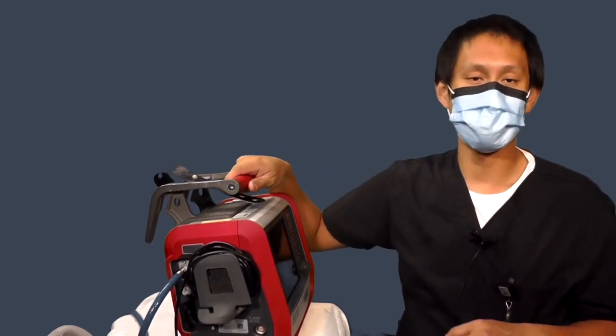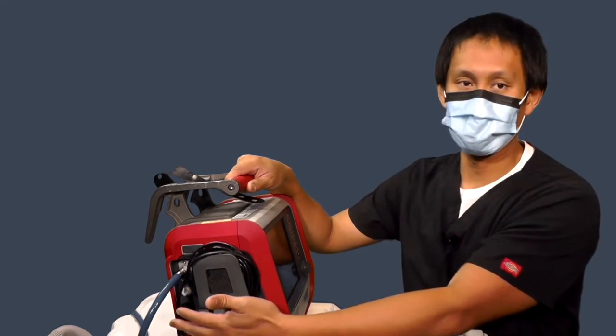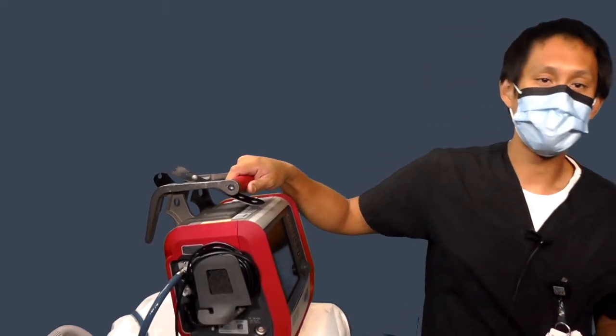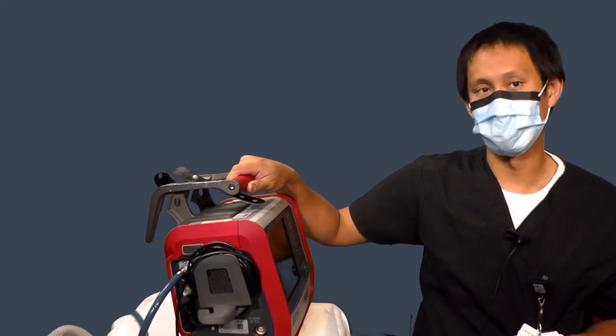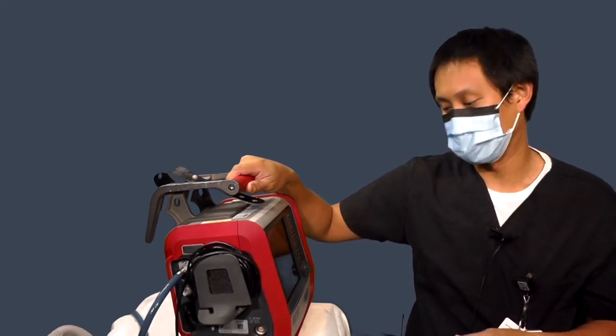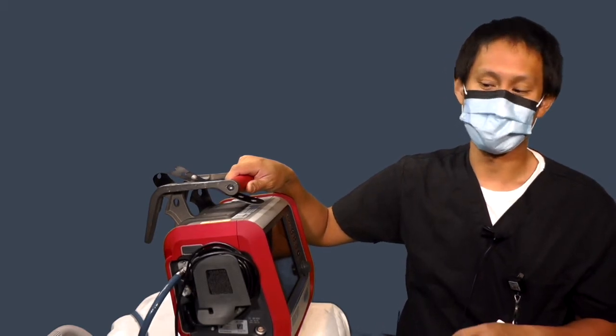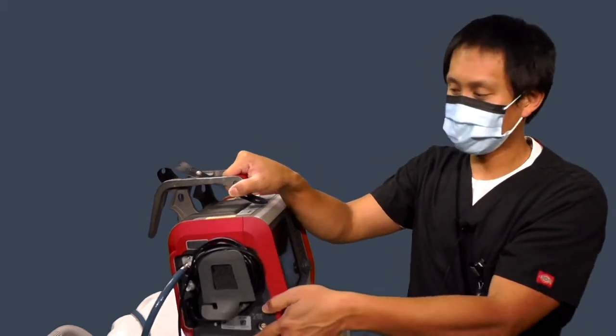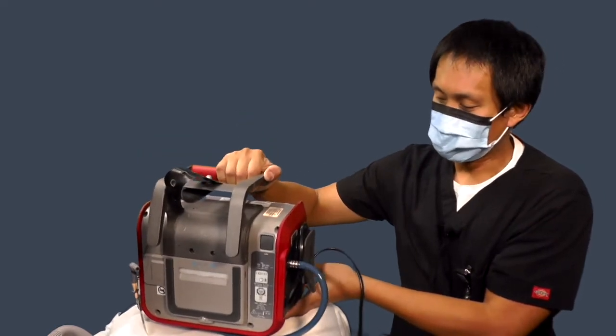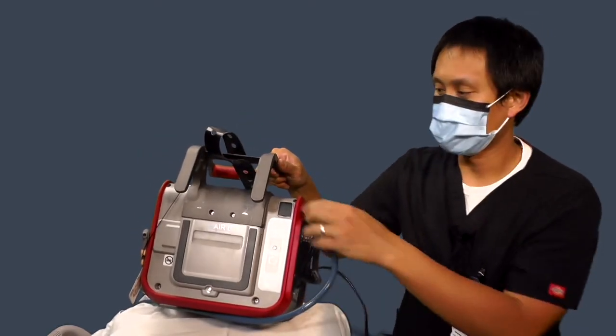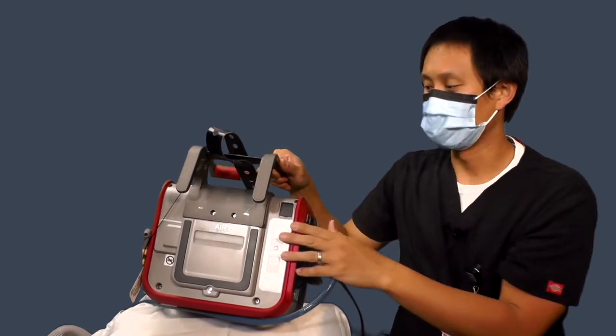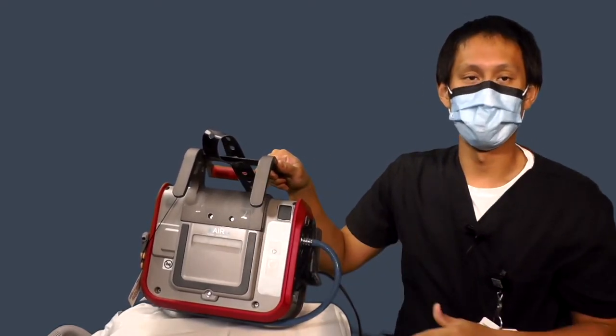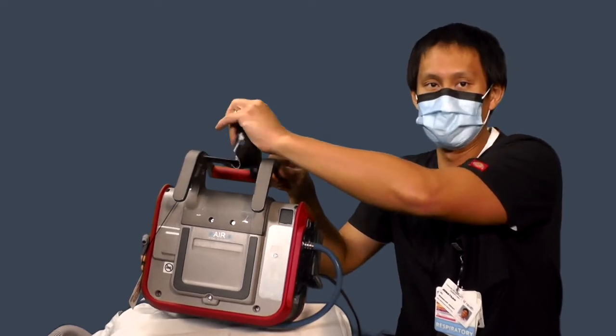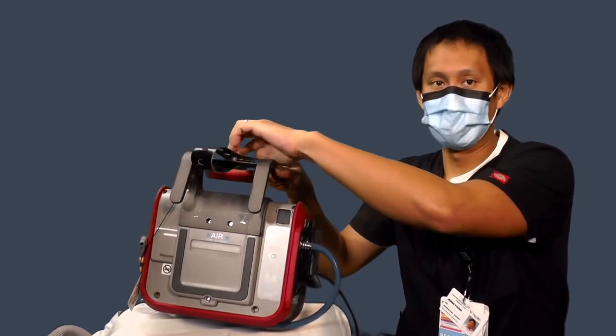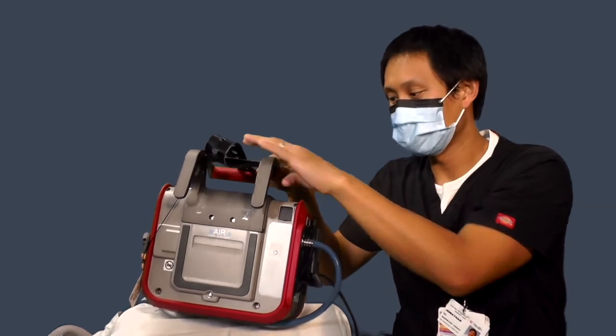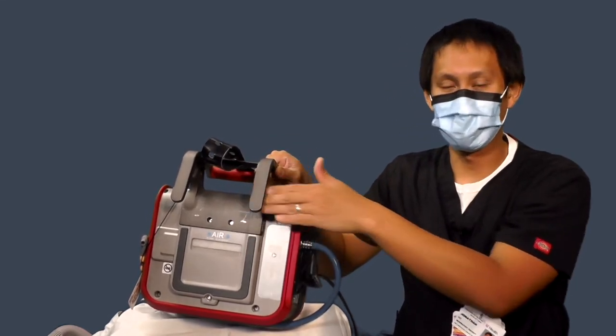If you do have a patient on room air, you do not have to plug in the O2 line unless you're expecting to use an O2 breath. Otherwise, you can run it on room air if you're trying to conserve oxygen. To rotate this around again, on the back, you'll notice the hooks that we mentioned earlier. You can hook this to a stretcher rail, but use the little leather strap to go over the rail, so that way when you hit a bump, it does not come off the rails itself.